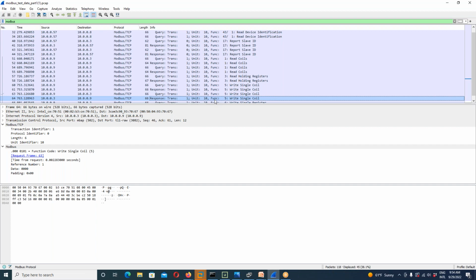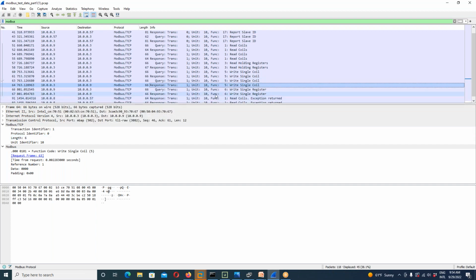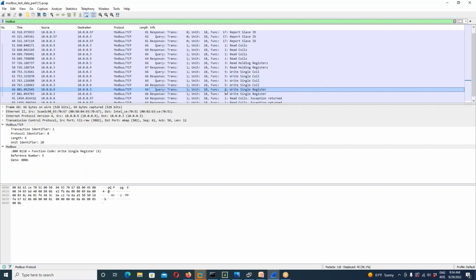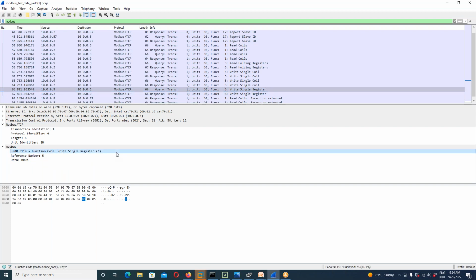These are all writing coils. And then we're writing a register. This is function code 6, right here—you can see it, function code 6. So now we're beginning to put values into the PLC.